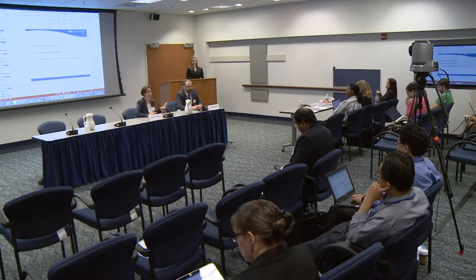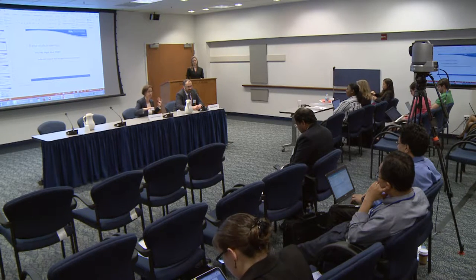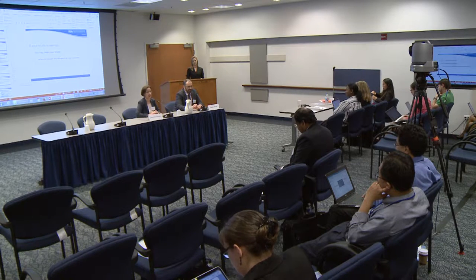First of all, I'm not sure that someone working in an academic institution that has so many people from different departments contacting you can say that you know it all. Plus, everything is always evolving. So I really would also say that our easiest submission and most smooth rides were when we contacted FDA. If anything, our challenge was to persuade investigators, because you always have situations when someone who knows someone had a bad experience and they don't want to talk, that really that's the best and, if you want, most cost-effective way, because you're ensuring that you're not doing experiments that afterwards will not be accepted as a part of your submission. So a pre-submission meeting is what we really encourage everybody to have.